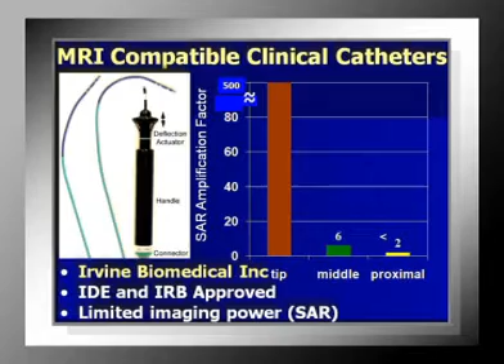This is just an index that radiologists like to use to indicate how much power is being absorbed around the tip. And it turns out that this amplification factor of 500 would translate into a rise in temperature of the tip of about 30 degrees centigrade. That would raise the temperature from 37 degrees to 67 degrees, and it only takes 50 degrees to ablate tissue. So this would cause ablation in undesired places. So this would be bad.